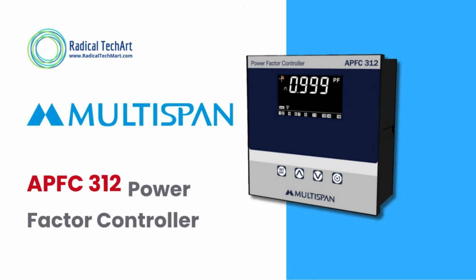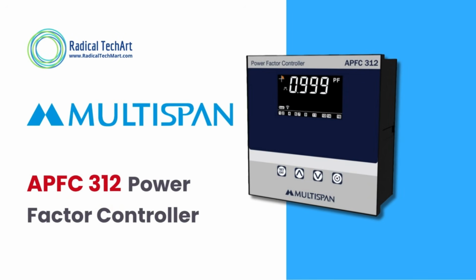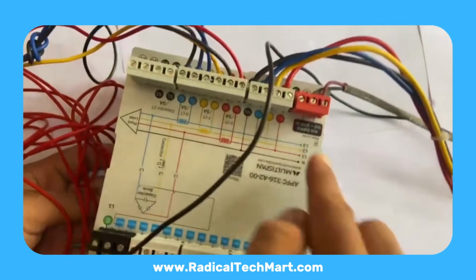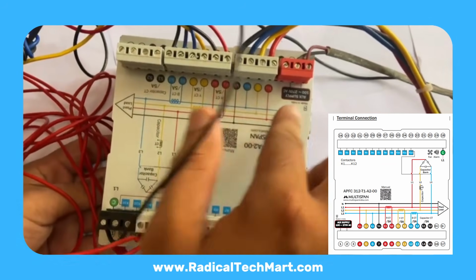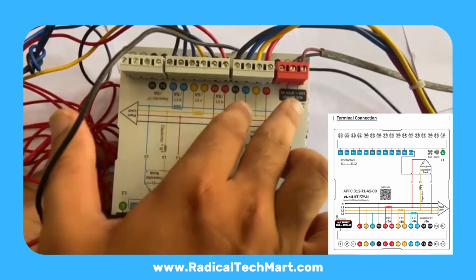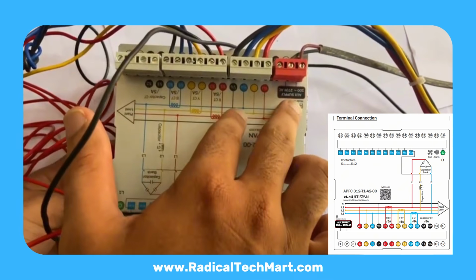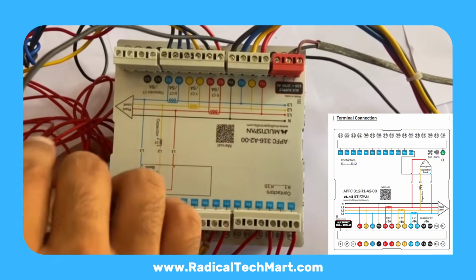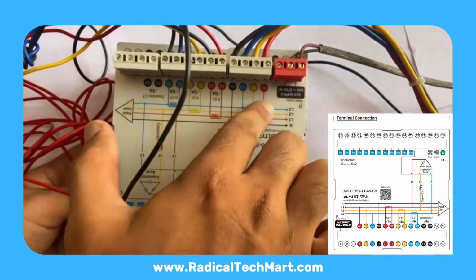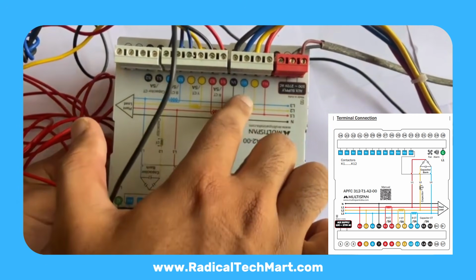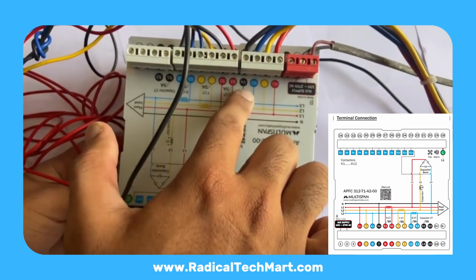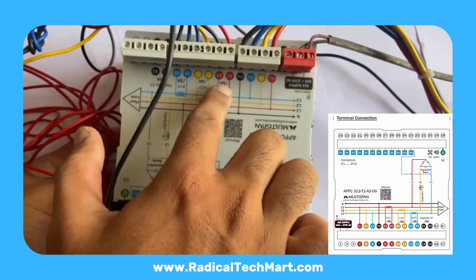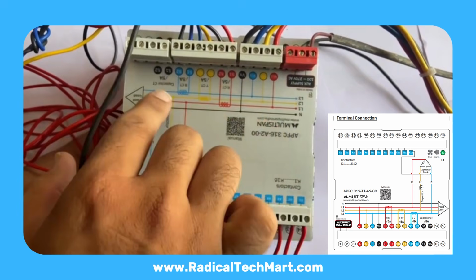Hello everyone. Today we are going to explain the APFC-312, which is an AC relay used for automatic power factor correction in capacitor bank panels. We have connected the power supply on terminals L and N, which supports input voltage from 100 to 270 volts AC. On the top side, terminals L1, L2, L3 and N are for your three-phase voltage input.